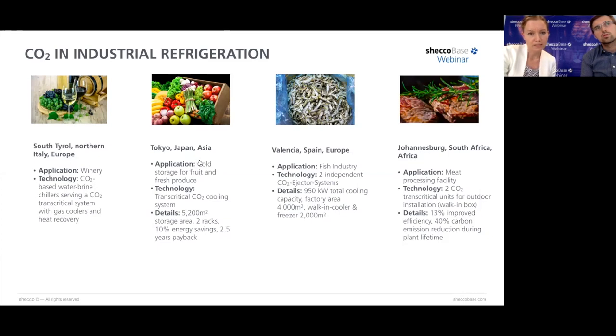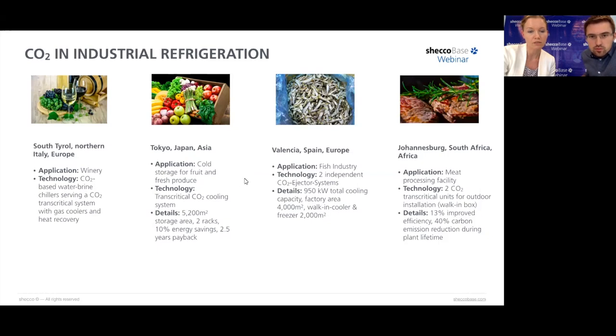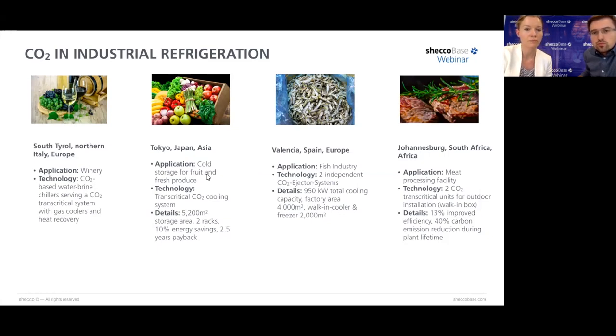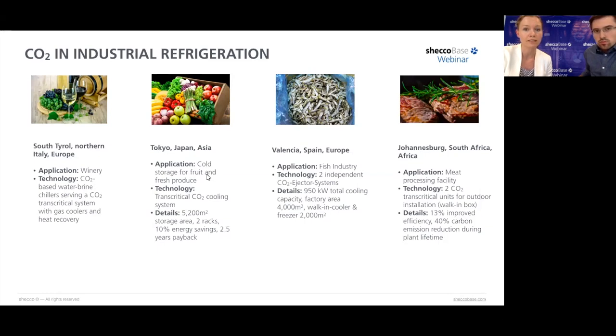There is a comment that in the US, at least for cold storage, the big driver is the regulatory environment, which is complex and expensive for ammonia systems regardless of charge level. Indeed, ammonia is a very common refrigerant in industrial applications, but in some countries like the US, regulations make it very difficult to use. In order to avoid regulatory compliance burdens, which can be prohibitive especially for small companies, it is easier to go for a solution that does not require the same level of notification and checking with authorities.